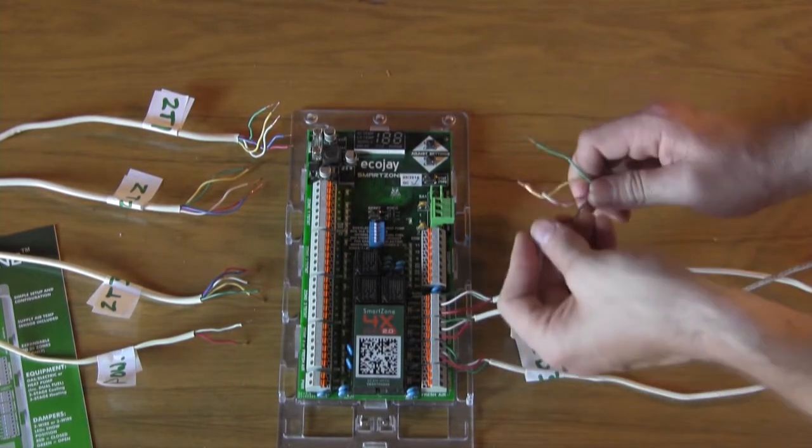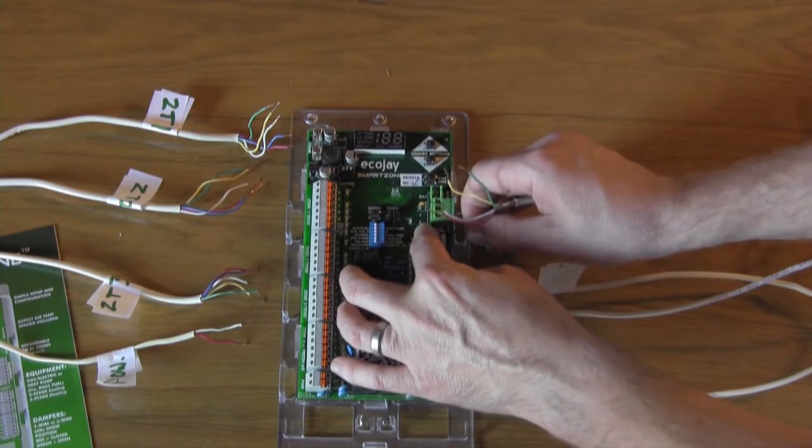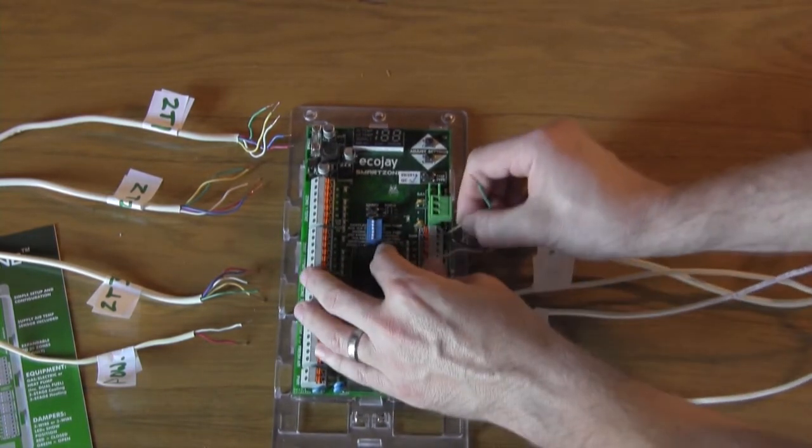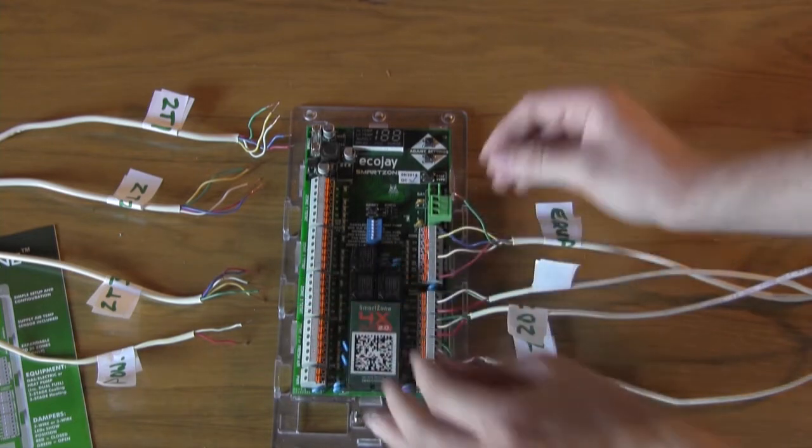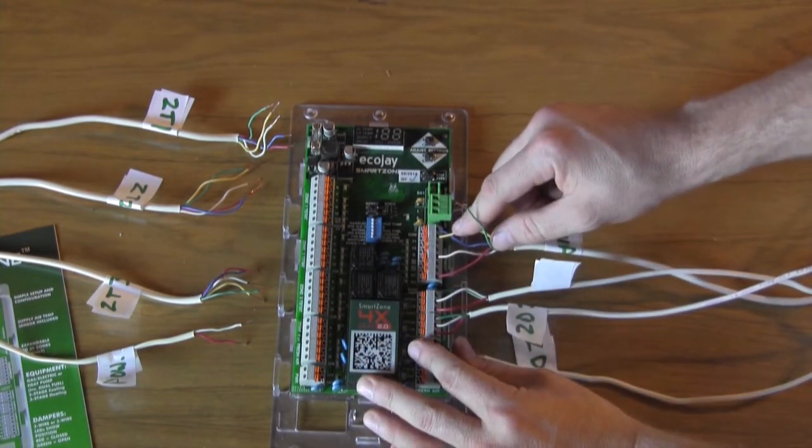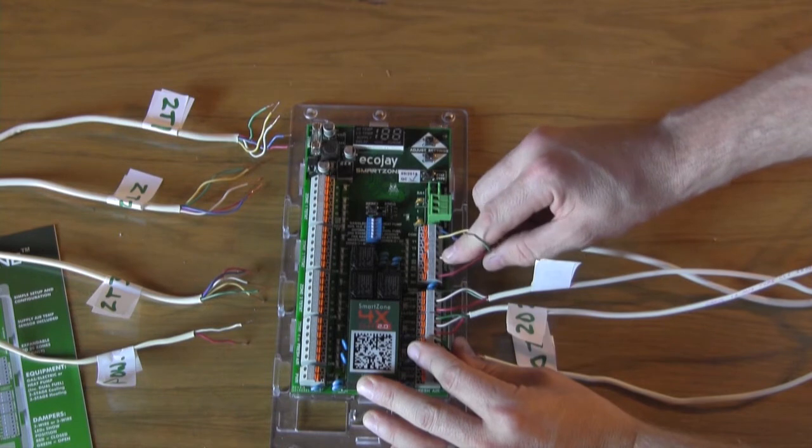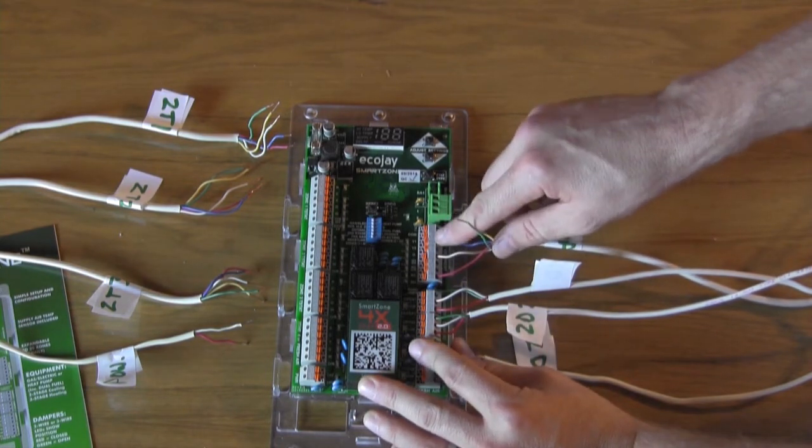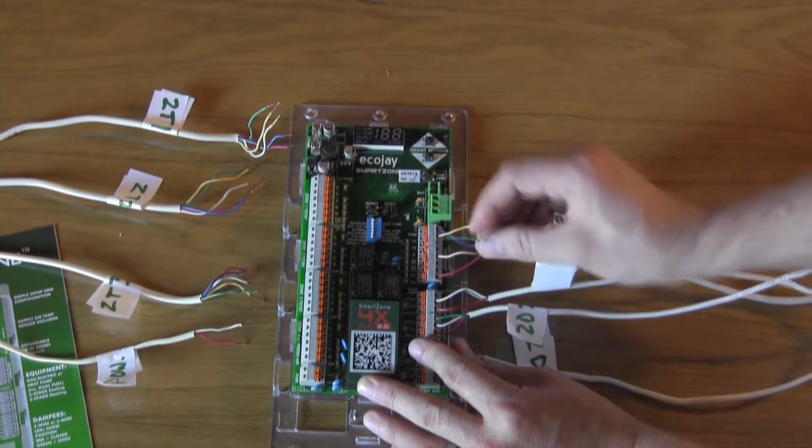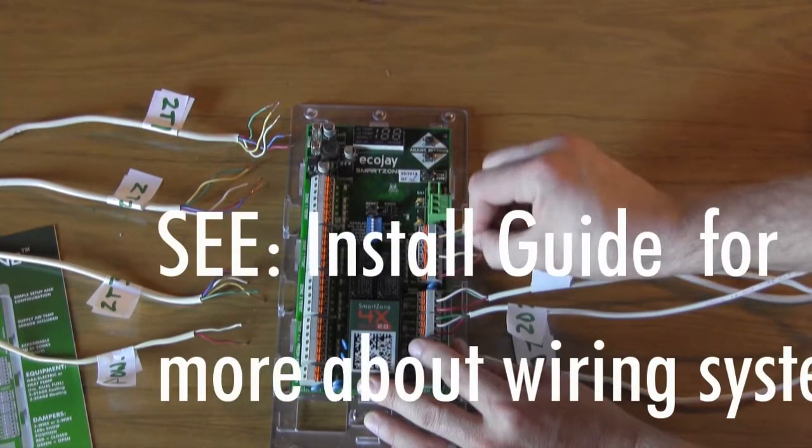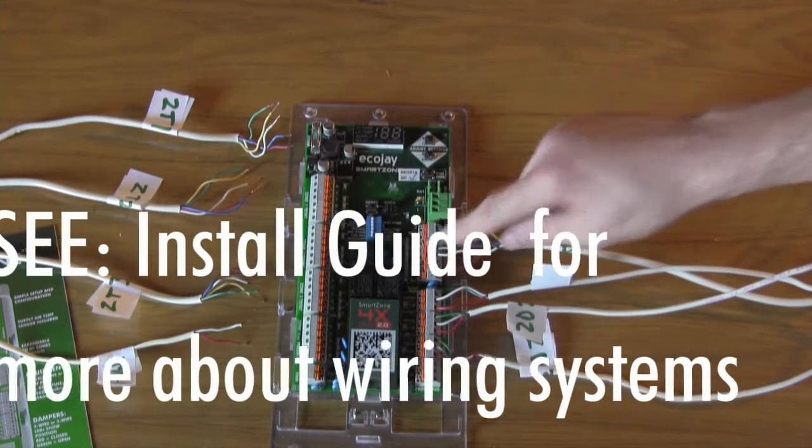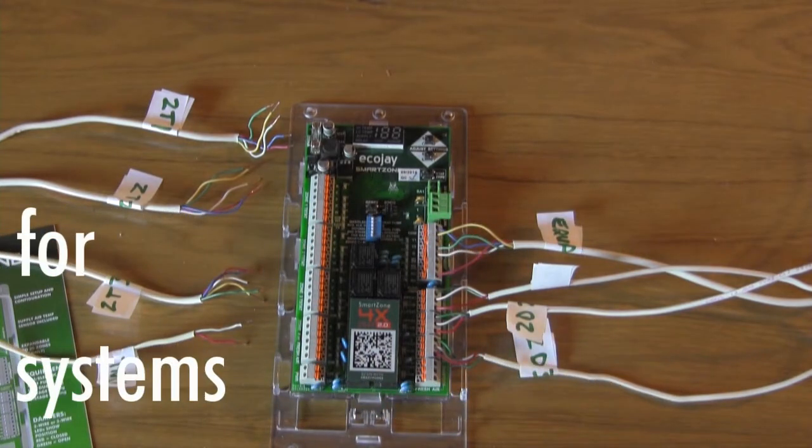We'll move to the equipment wires. This system is only a single-stage system, so there's only one Y wire and one W wire. Your system may be multi-stage and have a Y2 as well as a W2, or it may be a heat pump and have also an OB wire. Those terminals are labeled and any type of system can be used with the SmartZone.